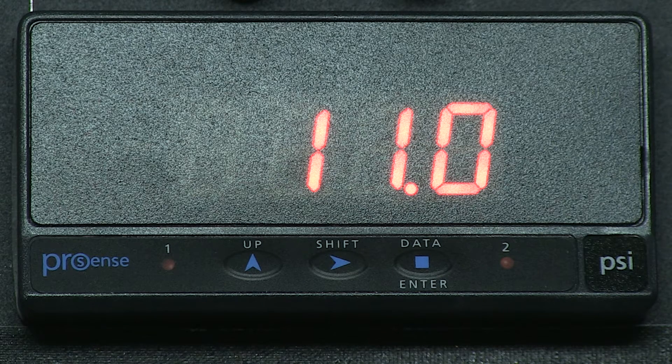In another video, we scaled our output to display the current pressure of our air compressor. The pressure transmitter is connected to an air compressor that has a maximum pressure of 60 PSI. Now we will set up the two relays with a high and a low alarm, so that the relays could tell an operator when the air pressure was too high or too low for production.